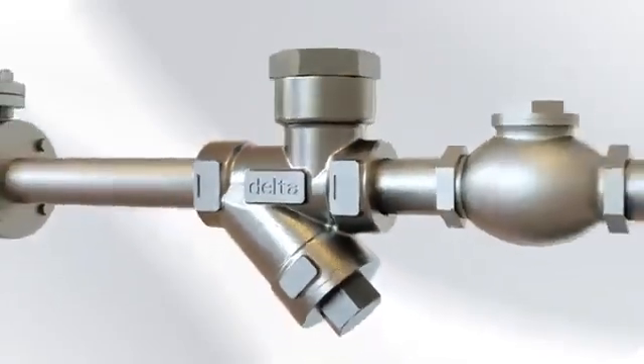As the pressure or load in the steam system rises or falls, the back pressure that is constantly changing at the mouth of the Venturi also rises or falls. This action gives the delta Venturi orifice steam trap the ability to easily manage discharging varying condensate loads in a steam trap that has no moving parts, while still keeping the steam in the system.